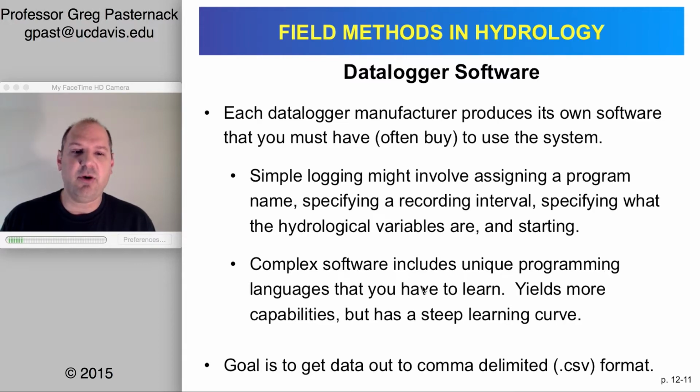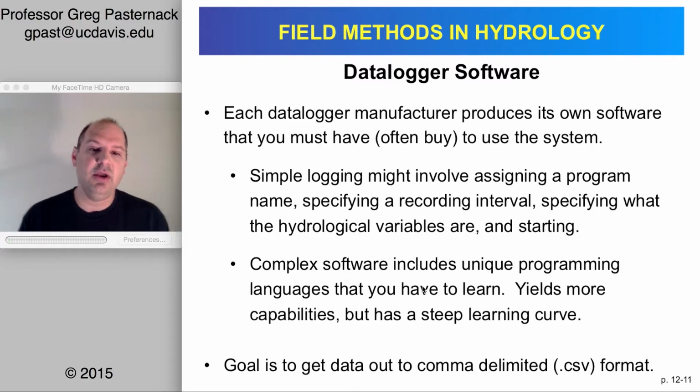However, a simple logging program could be saying, okay, let's create a logging plan in the software. So I'm going to specify a project name. You'll specify the recording interval. So if I'm in a well, it might be once a day. If I'm in a river, it's typically going to be 15 minutes. You have to then say, okay, here's the kind of sensor I have, and that could be a drop-down list or something. So once you've picked the sensors, it knows the information about that and it can go.